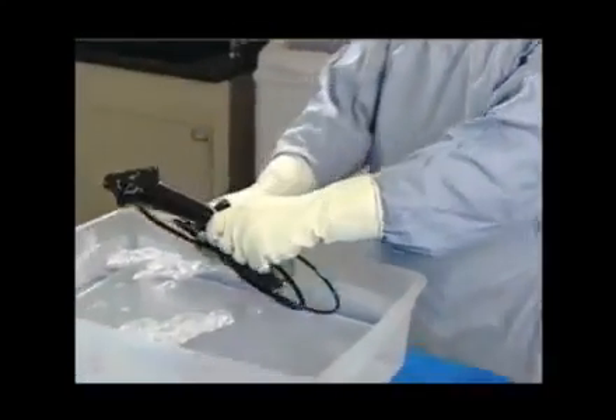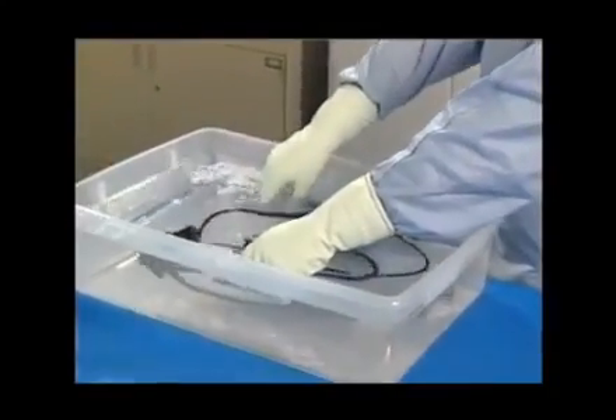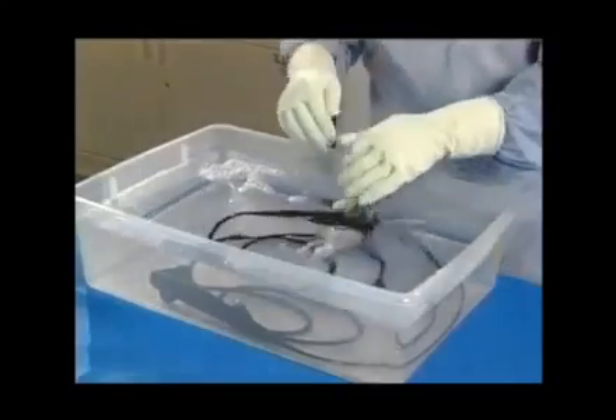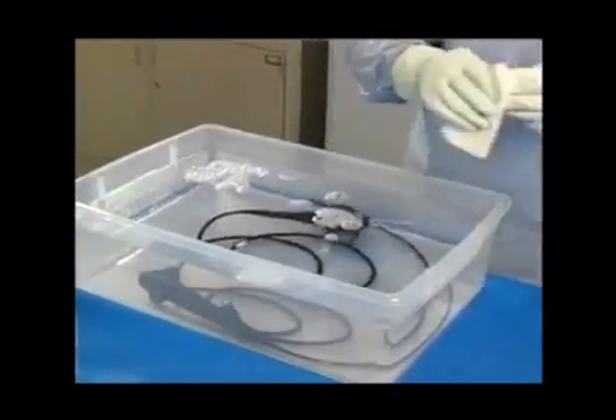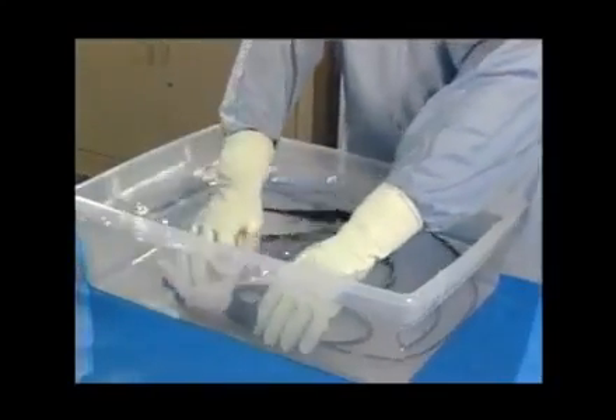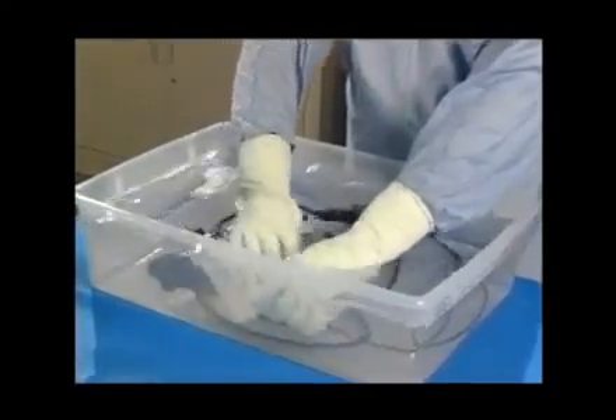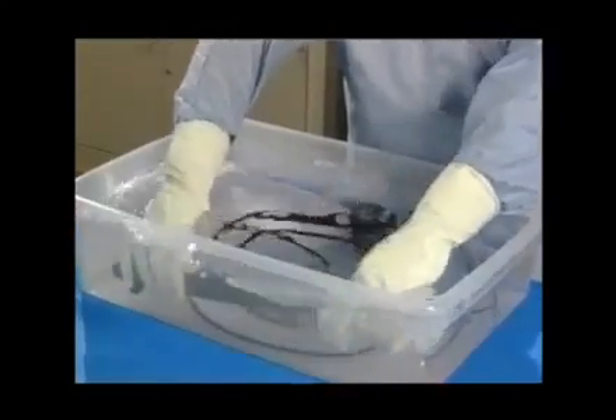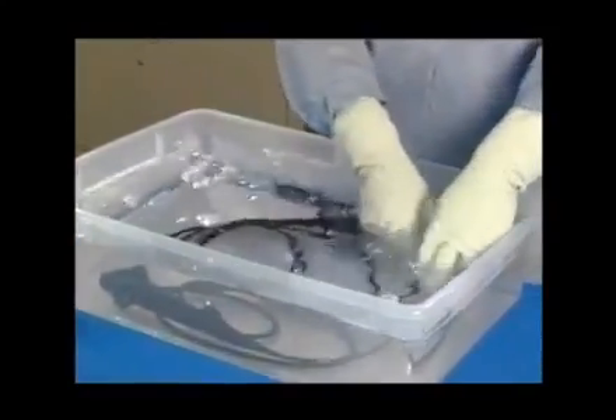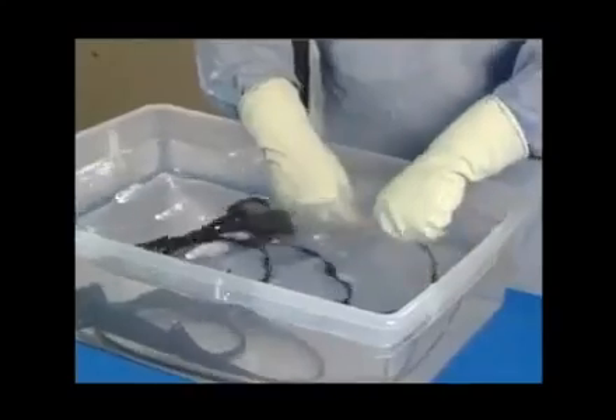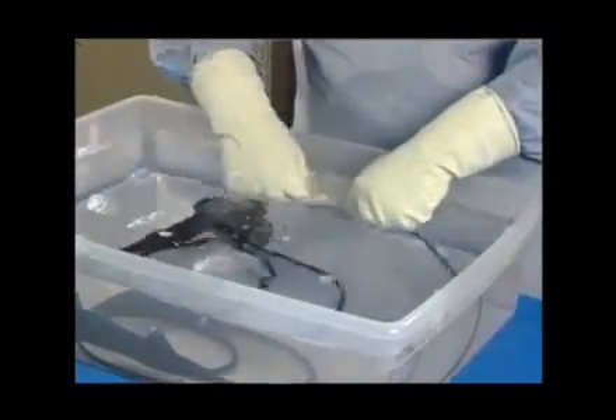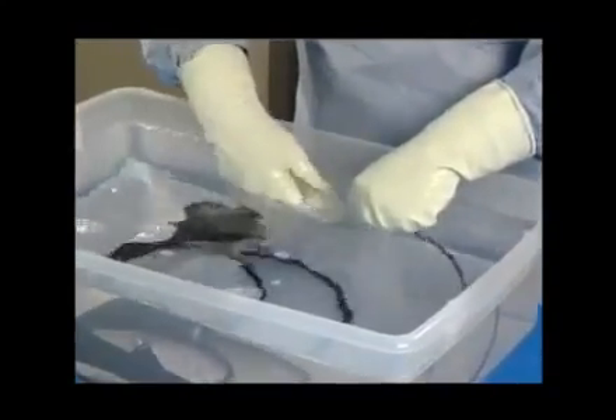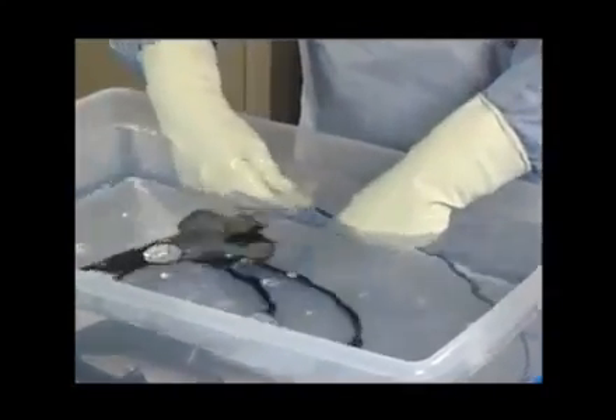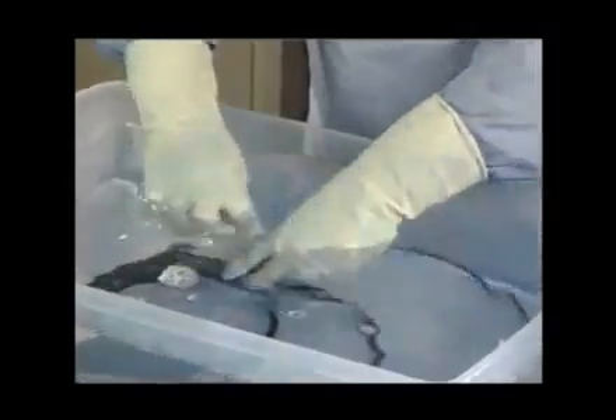Carefully coil the bronchoscope and completely immerse it in the detergent solution. Use a soft brush or a lint-free cloth to clean the exterior surface of the bronchoscope. Pay particular attention to cleaning the distal tip. Take care not to scratch the small lenses. Perform all washing while submerged to prevent splashing.